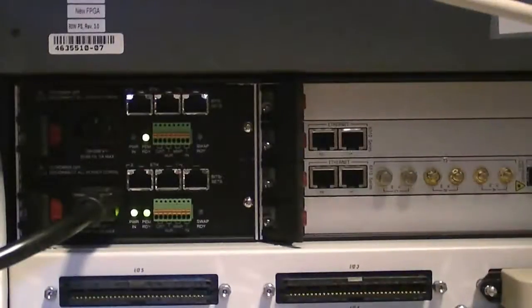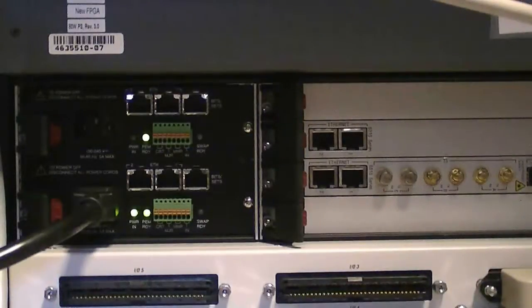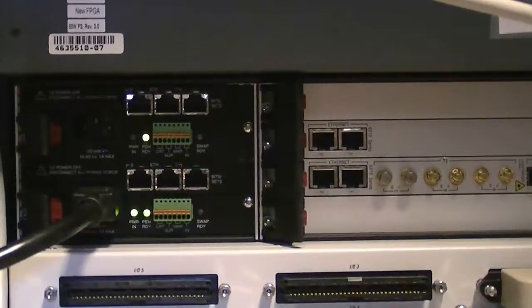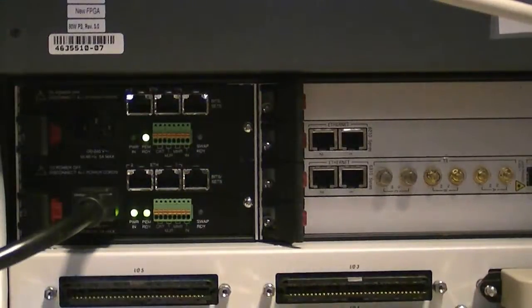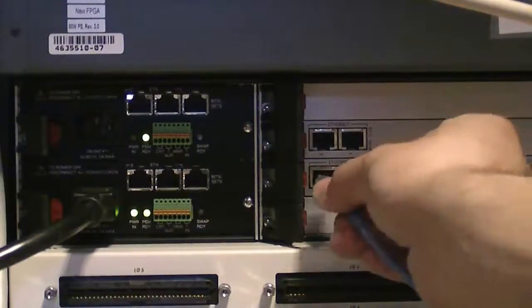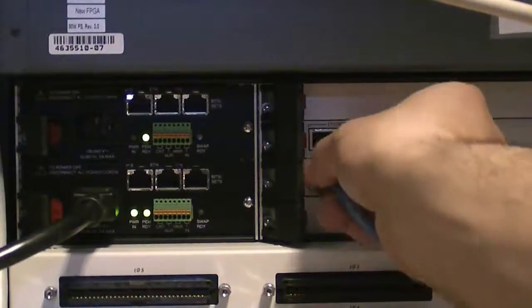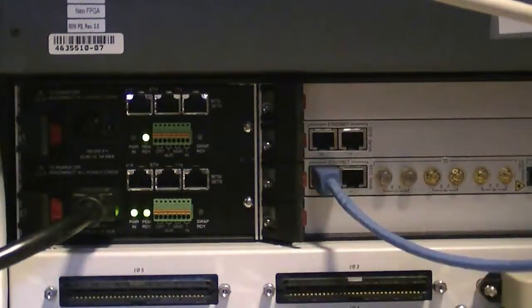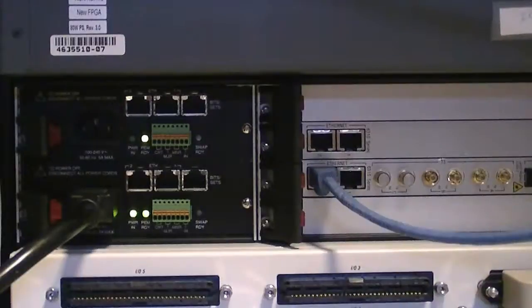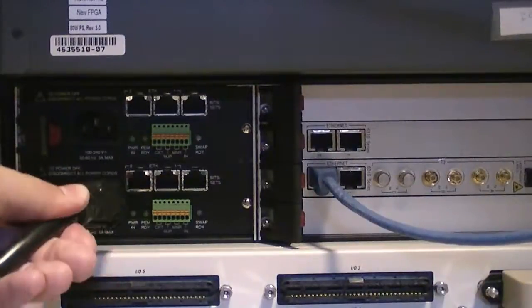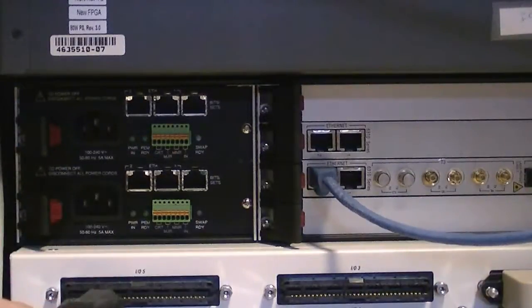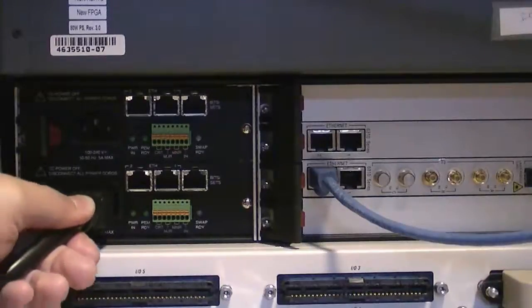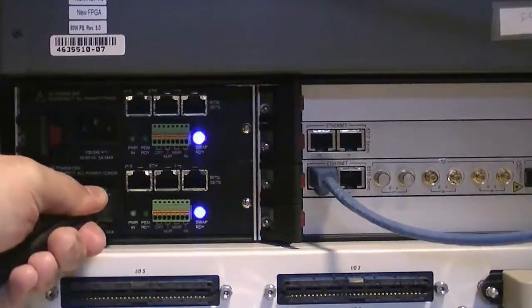With the BootP server application configured and open on the laptop that will be used to provide configuration information to the gateway, connect a crossover cable to one of the network ports of the primary TP board. At this point, the power may be removed. After waiting up to a few seconds, reconnect power to the gateway.